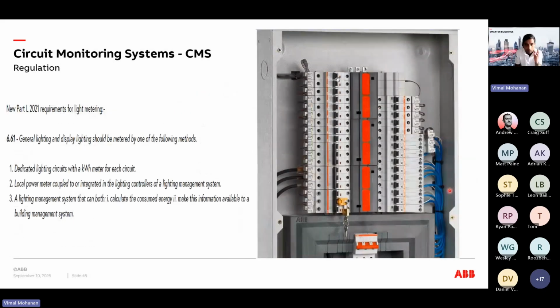For the guys on this call who are more commercially driven, you're probably already aware of this. In early 2021, the Part L regulation came in saying that if you're using a split metered board, or a board that does your power and lighting, traditionally seen in commercial installations, with dedicated lighting circuits, you need a kilowatt hour meter for each one.